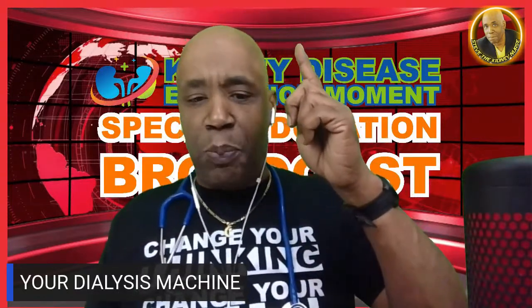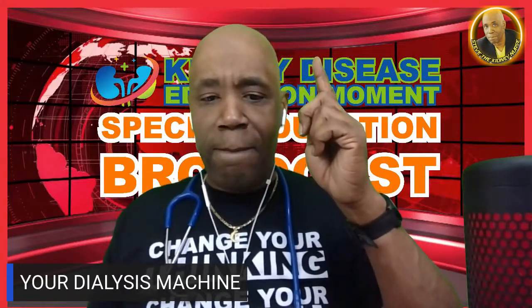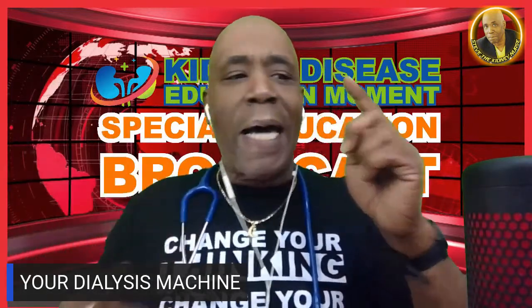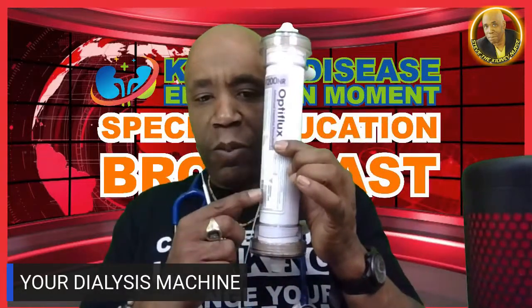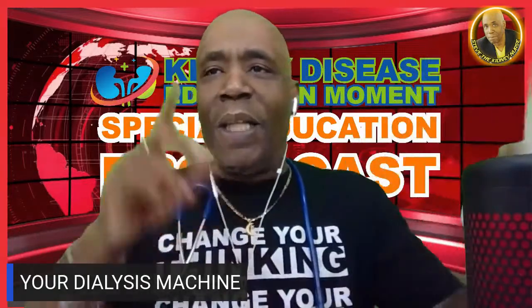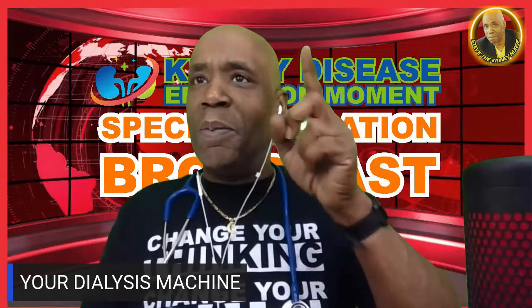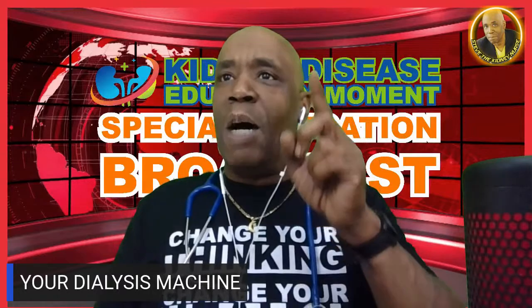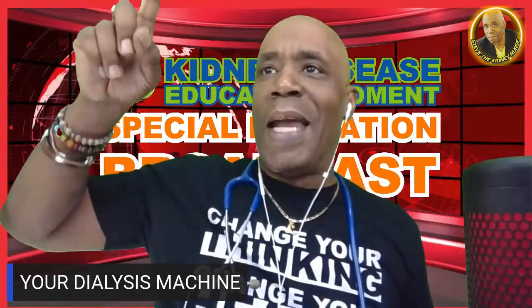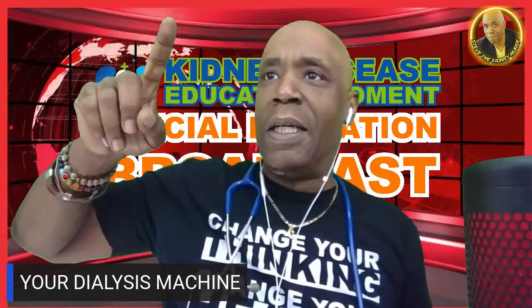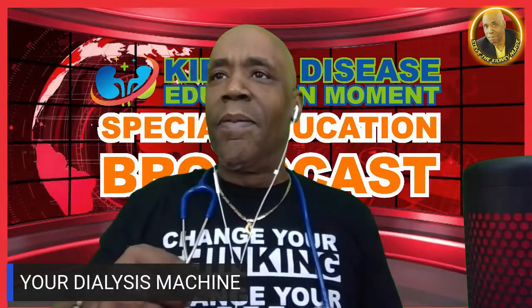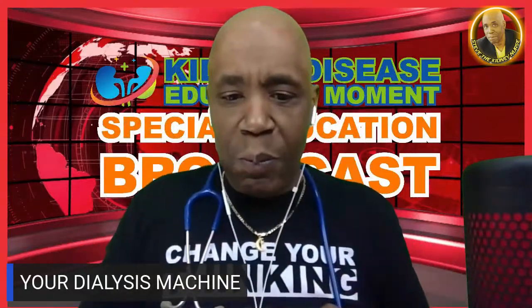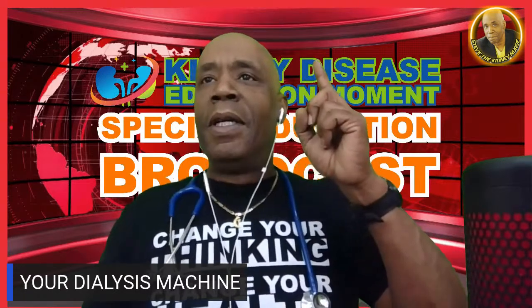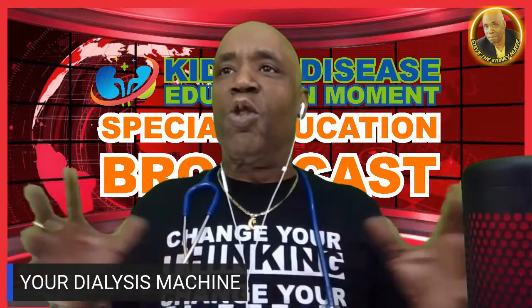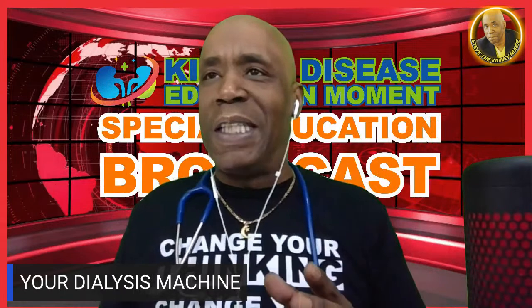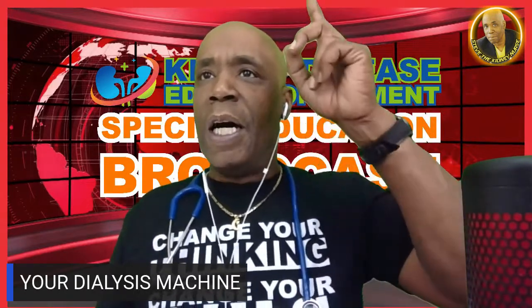Number one, let's look at this pump. This pump right here keeps the blood flowing from the body to the dialyzer and back into the body. So as you can see, this pump is pulling the blood from the arterial line, it comes through the pump, goes through the filter, comes out, goes down into the venous line and back into the patient. And it's a constant rotation. Okay? Now, sometimes they may have to reduce that pump speed. You may have some issues with your arm, your catheter, or you may feel sick, and they may reduce that pump. You can see right here the pump speed.